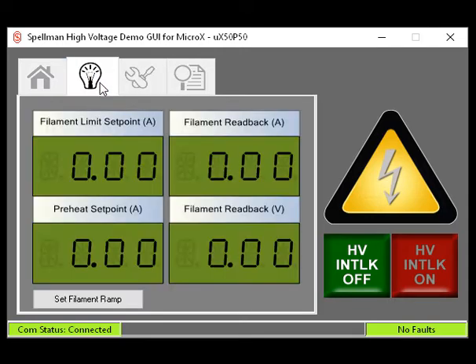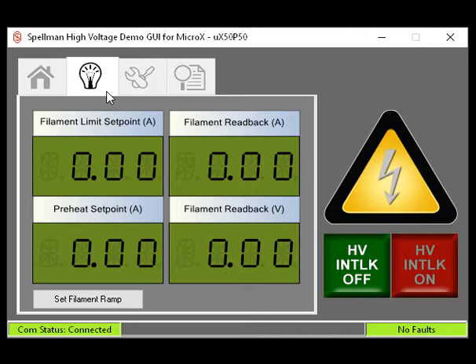The Filament tab, indicated by the light bulb icon. This tab allows you to set the filament limit set point. This is the maximum current the filament power supply will provide to the filament. To protect your X-ray tube, you must confirm from the X-ray tube manufacturer what the maximum rated filament current is.